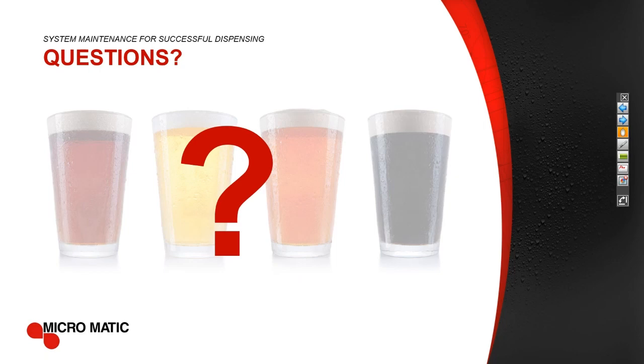Yeah, great point, Dave. Question from Matt, should I turn off the glycol power pack during cleaning? That's a great question. Matt, that's one of the questions that has been in my 20 years as well. Personally, I always say no. If I'm using a recirculating chemical cleaning method, as long as the water's moving, it will not freeze. A lot of techs are concerned about the water freezing in there.